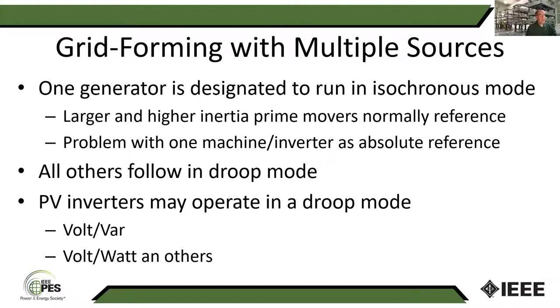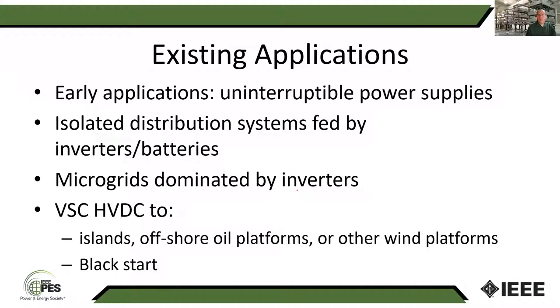If you do this, you need to have some way of doing some equivalent to dispatch to make sure that the other inverters and other generators in the system are able to supply power. And so you may have some sort of frequency droop or voltage droop, or you could have some sort of a volt-watt type of scheme. So there are a number of ways you can try to control these for doing the sharing. Some applications that already follow some things like this are uninterruptible power supplies when you have multiple inverters acting as this, isolated distribution systems that are fed by inverters with batteries, voltage source converter HVDC schemes that are connected to offshore oil platforms or offshore wind platforms, offshore islands, or trying to do black start.